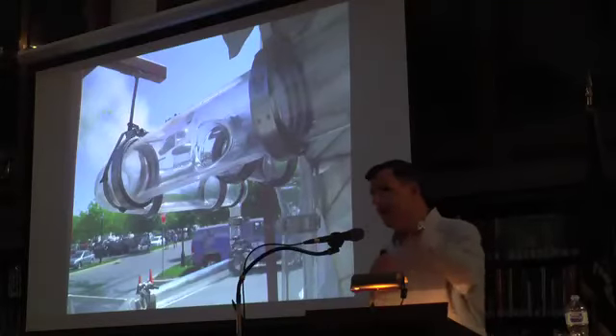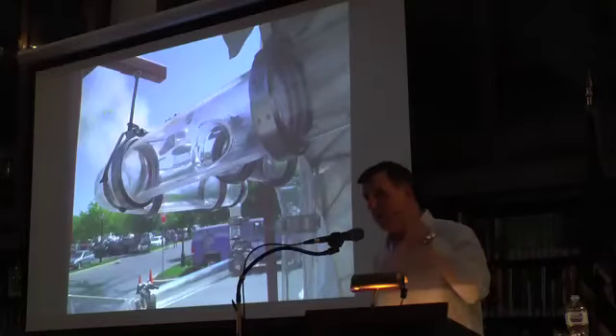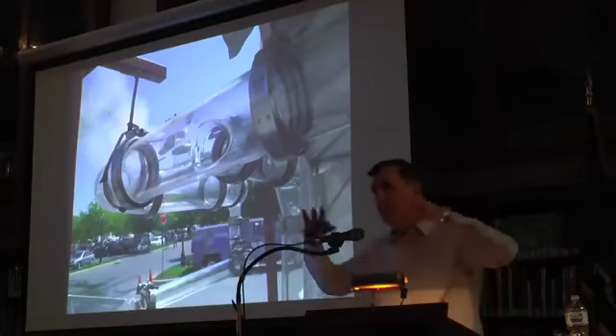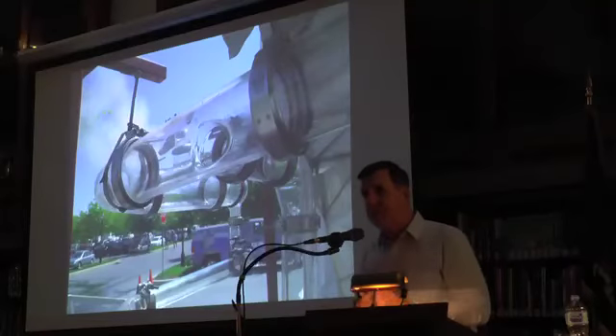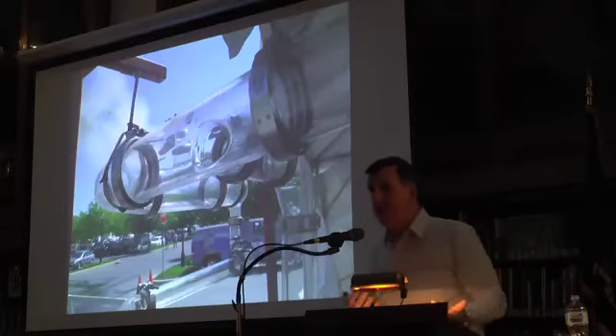When you look in a gauge glass on a boiler, everything above that water line should look like that. It should look like there's air in there. That's dry steam. So this is a boiler producing dry steam, but look at how it's doing it. This piping that's around the boiler is considered these days to be a part of the boiler. This is the stuff that separates the steam from the water. And you go against those directions at your peril.